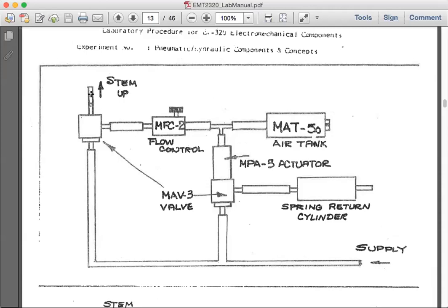From the moment you press down the stem, the pressure builds slowly, then eventually activates the actuator and the piston shoots out. So in terms of action, you activate the stem, you have approximately 5 seconds. Let's keep it standard with the release. So you have a 5 second time delay, and then the piston shoots out.